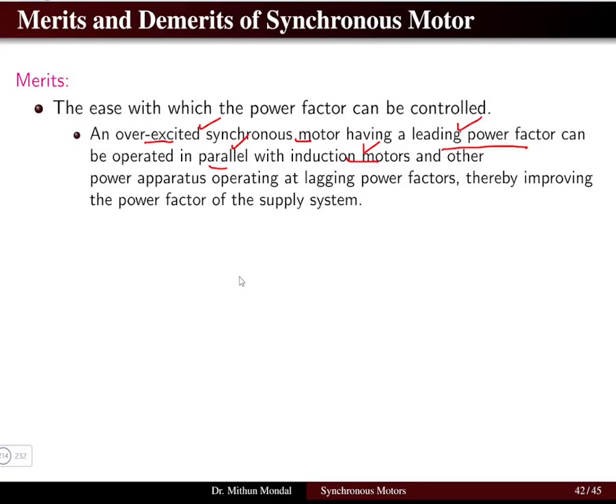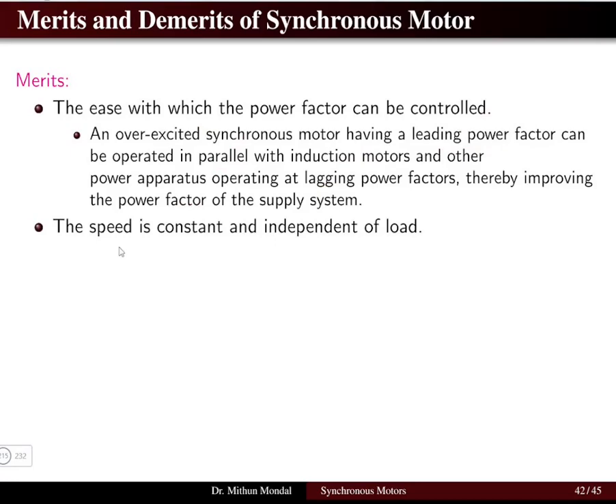By connecting the overexcited synchronous machine — operating at leading power factor — in parallel with the induction motor, the power factor of the supply system improves. The lagging power factor caused by the induction motor is corrected by the overexcited synchronous motor.